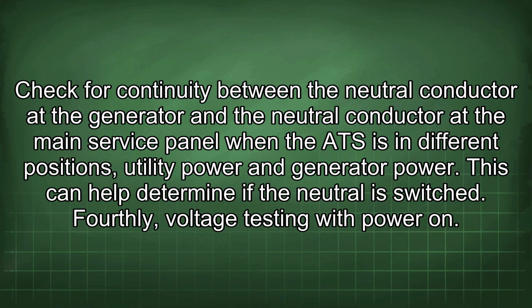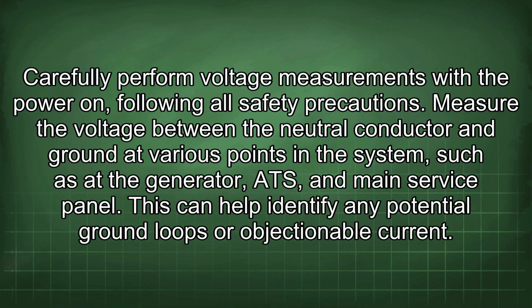Fourthly, voltage testing with power on. Carefully perform voltage measurements with the power on, following all safety precautions. Measure the voltage between the neutral conductor and ground at various points in the system, such as at the generator, ATS, and main service panel. This can help identify any potential ground loops or objectionable current.